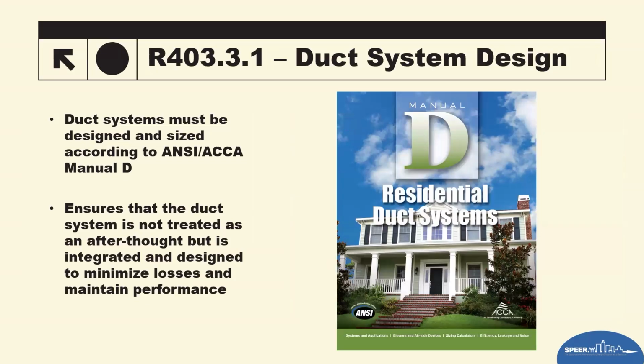Duct system design: we've always had Manual J and Manual S required in the code, in the mechanical code. We're doing sizing from load calculations of Manual J, and sizing of the equipment with Manual S. Now it's bringing in Manual D. So now we're going to look at duct design.